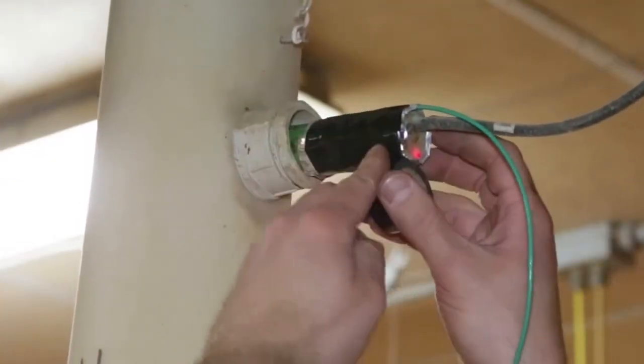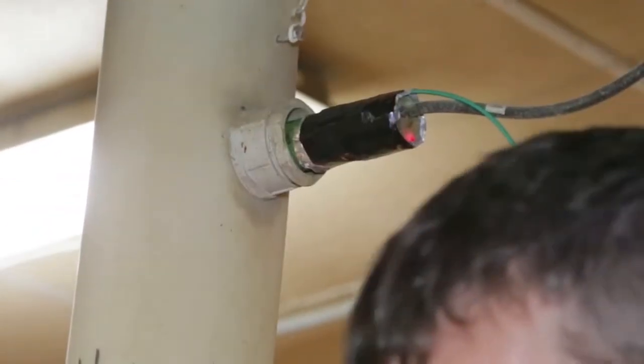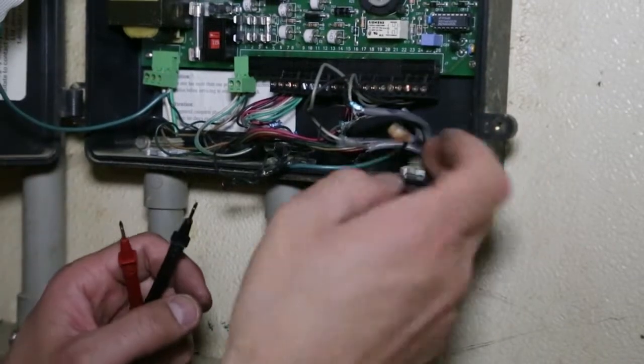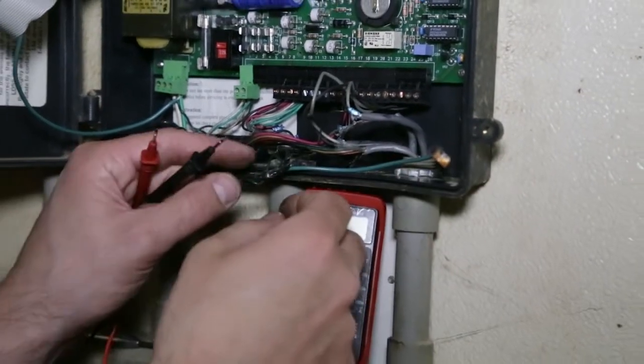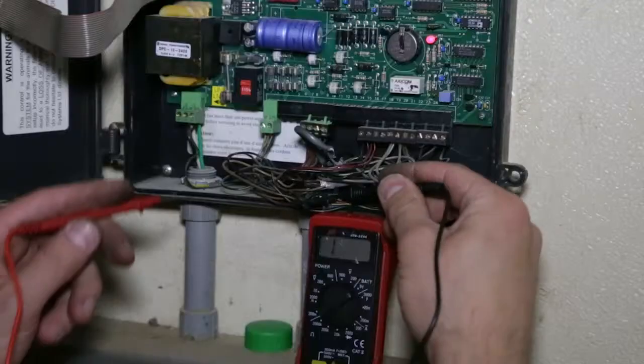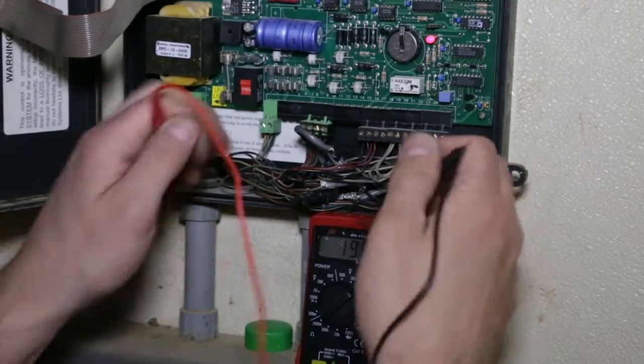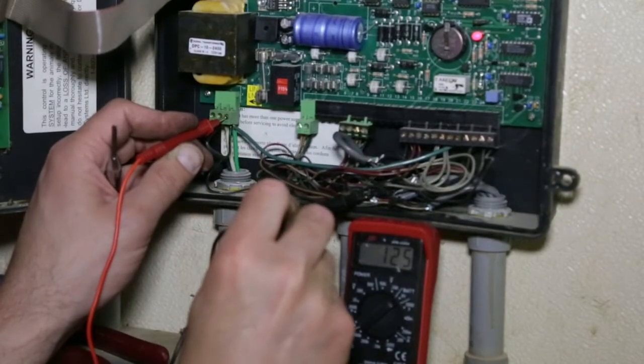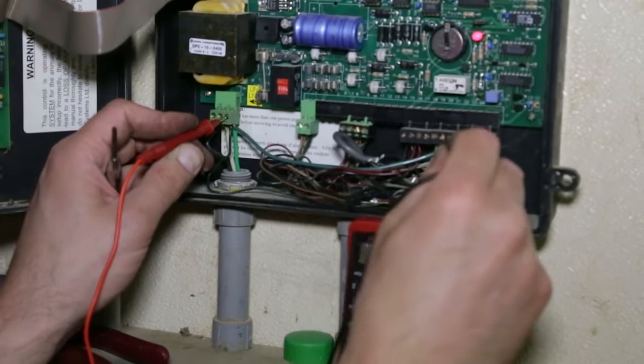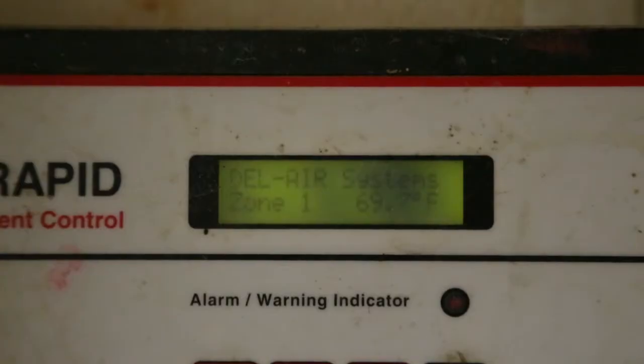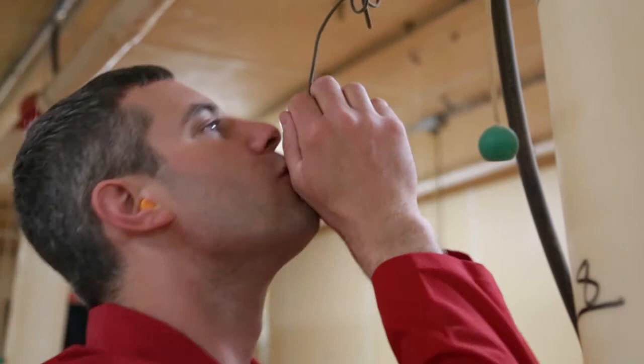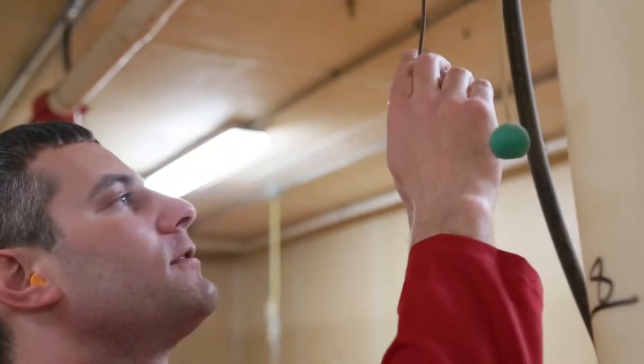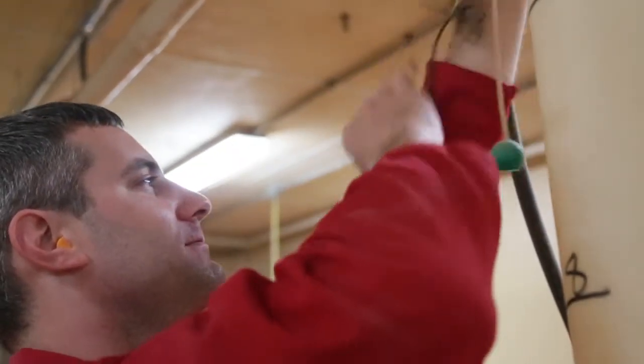If you are unsure that a sensor or piece of equipment has been grounded, as a precaution, disconnect the sensor wires from the computer, but not from the earth ground prior to plugging in the EPI system. Measure the static charge on the sensor wires before and after plugging in the EPI system. The measured voltage should be the same if properly grounded. If okay, reconnect sensor wires and test sensors. After grounding all sensors connecting and grounding the automation wire while the power supply is plugged in, make sure the sensors work and that no static charge is building up on the sensor wires or tip.